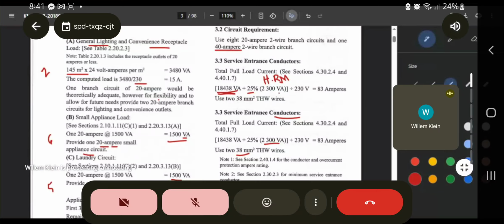But sir, what if I want to separate the computation? You can also do that, but instead of 25%, you will subtract 2,300 from here. So that's I think around 16,138. Okay. So if you excluded this highest rated motor and then plus, instead of 25, you'll use 125% times the 2,300 VA. Okay, is that clear? No? So to avoid confusion na, the 2,300 VA highest rated motor is already included here. So you will just add another 25% of your highest rated motor. But if you want to compute separately, you'll use 125% of your highest rated motor. So that is for the conductors. We're computing for the conductors.